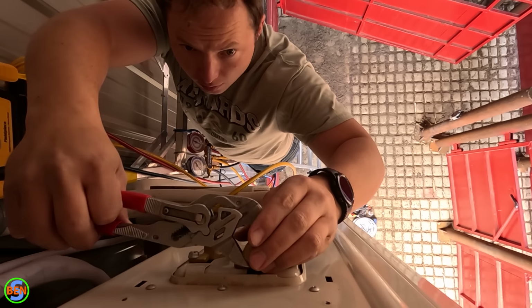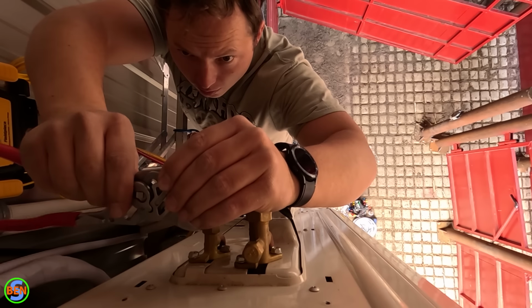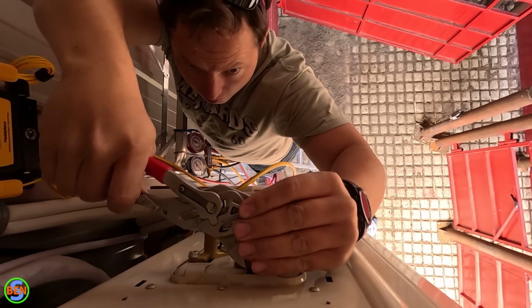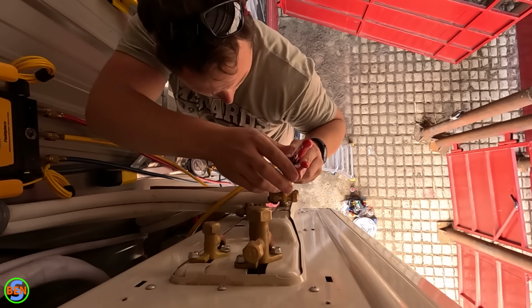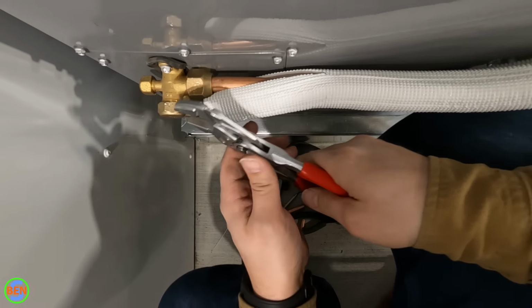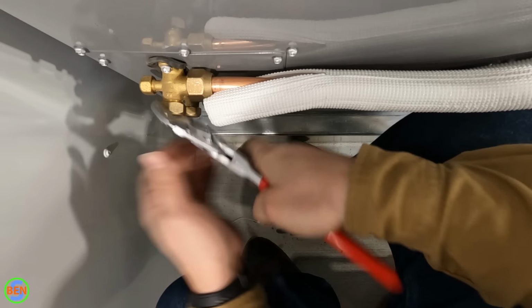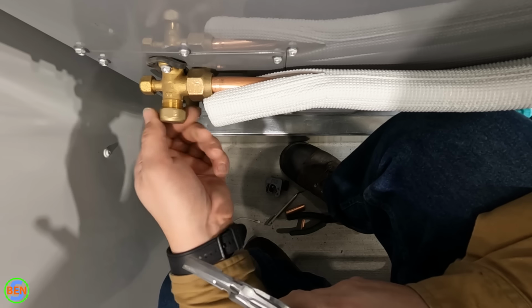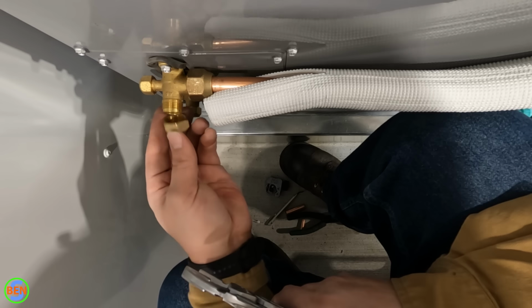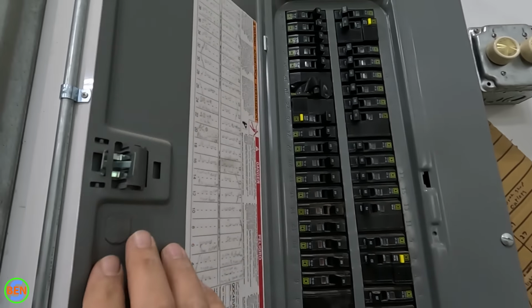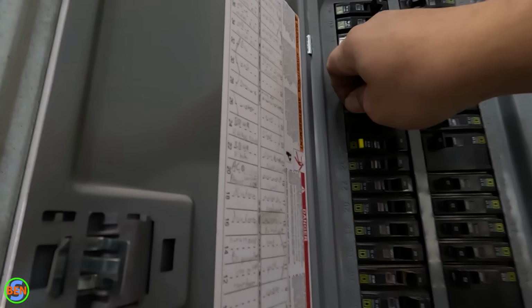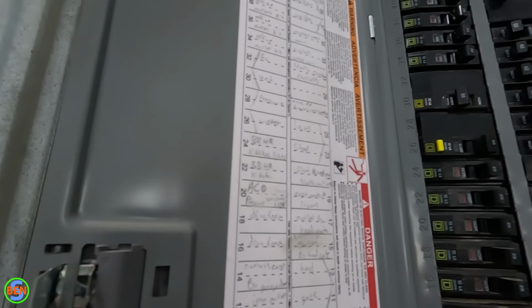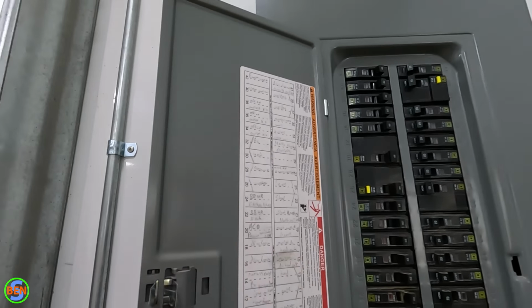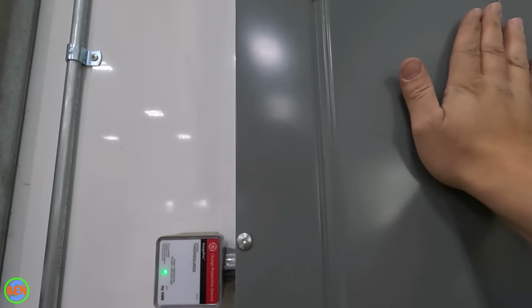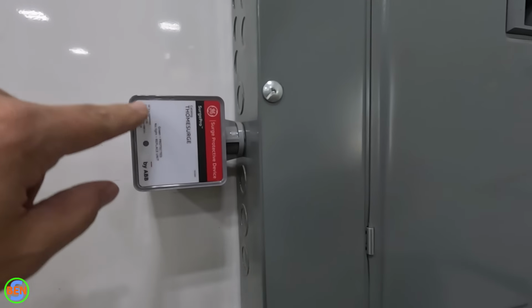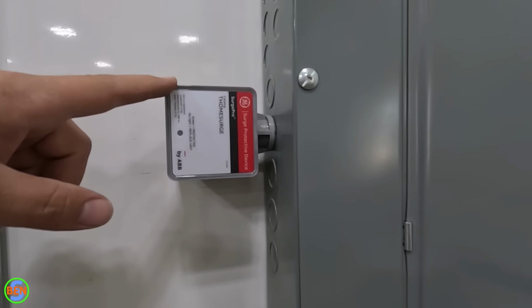On this particular unit, most of the valves were already open. I just had to open the two primary valves on the outside unit, and I think that that's all. Maybe I had to open them on the air handler unit as well. But just make sure all of the valves are properly opened, and then we are ready to move on to the system startup. Obviously, it's really not a good idea to start the system if any of the valves are closed. On the wall-hung indoor units, there are not valves that you have to open. It's just a matter of connecting your line set. Note that you should really install a surge protector with every mini split installation.